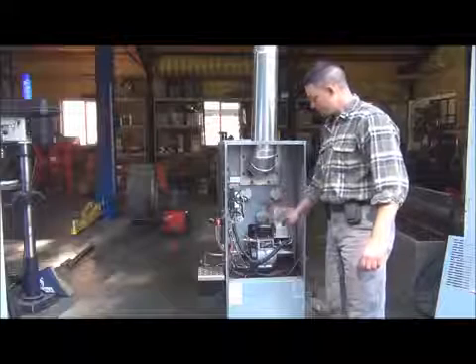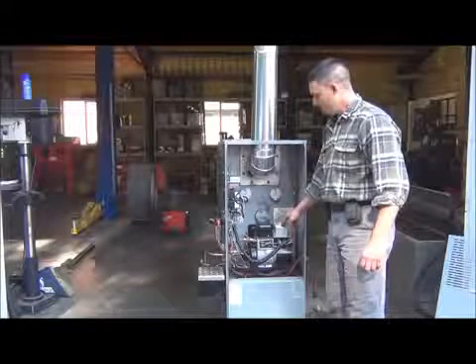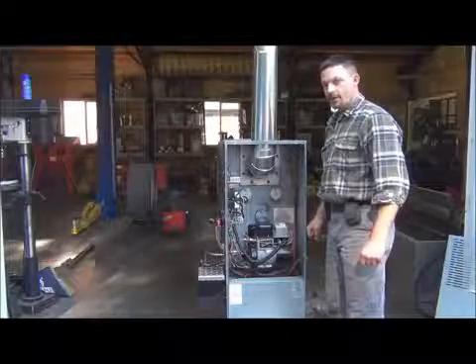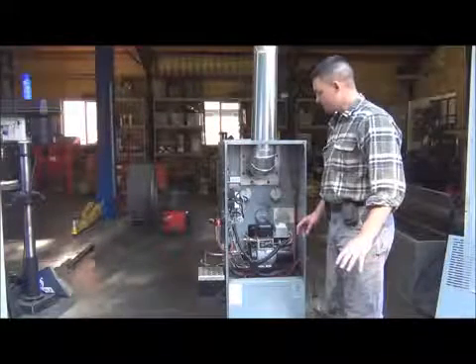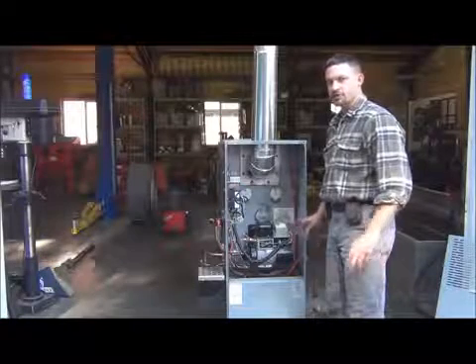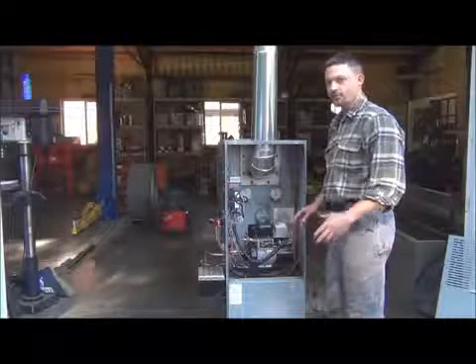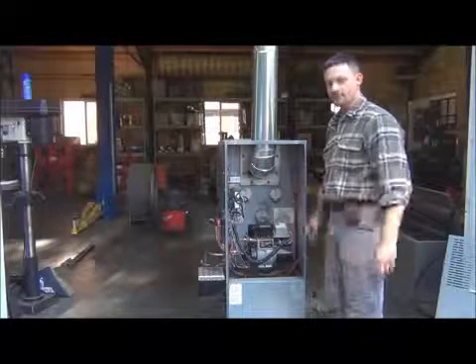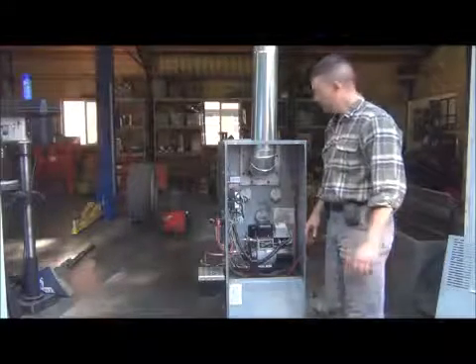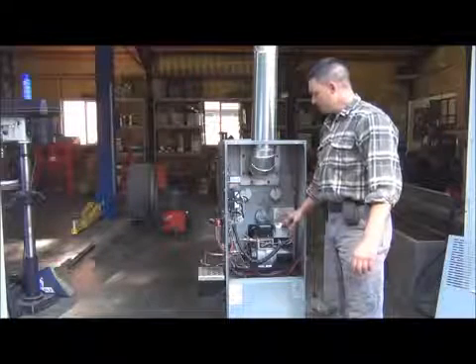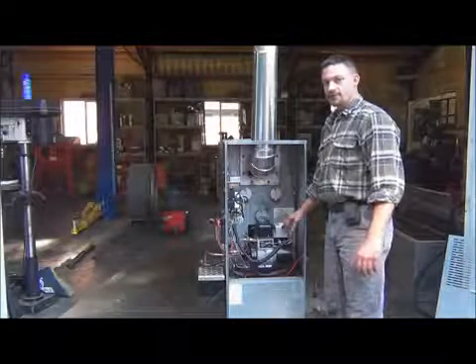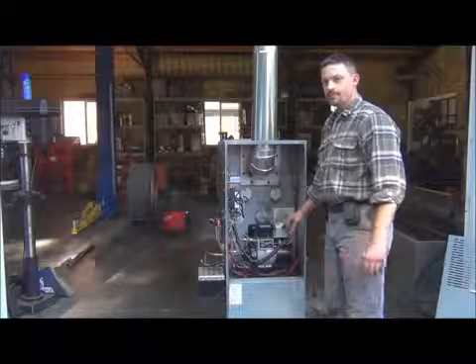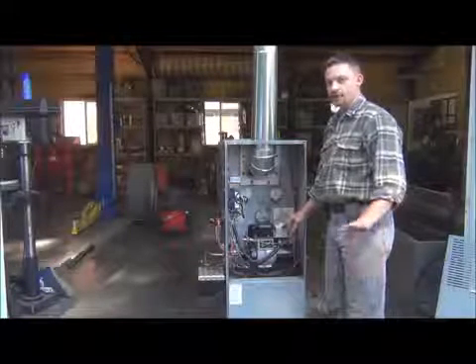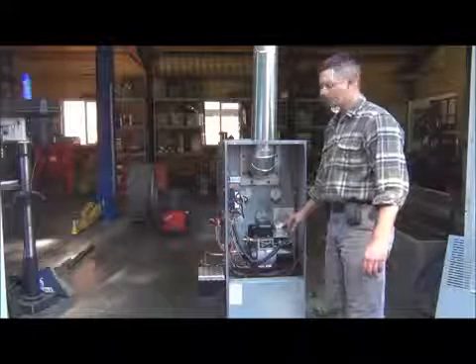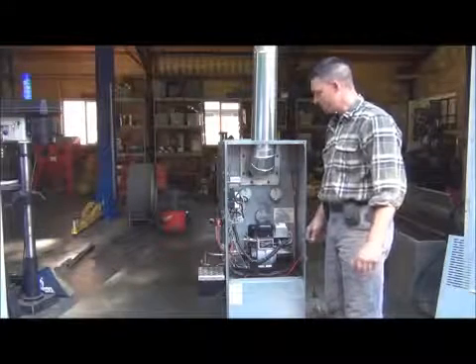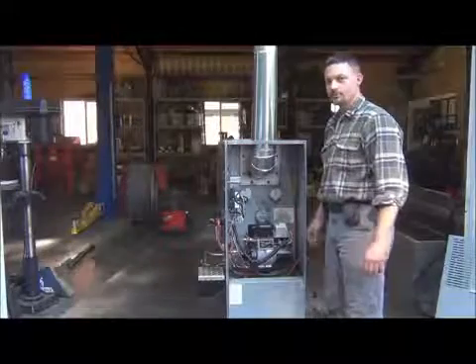And then I've reused the existing primary safety, and what this does is it has a flame detector down inside the tube, and it won't allow the burner to light if it detects that there's already flame in the heat exchanger. Meaning if you spilled some oil in there and there's a fire burning in there that's not supposed to be in there, it won't allow the burner to spray any more fuel in. And what else it does is, if the burner doesn't light when it's supposed to, after a small amount of time, it locks the burner out and prevents it from spraying any more unburnt oil into the heat exchanger. So if you come out here and this red button's popped up, then you know that you got some kind of problem. For some reason the burner wouldn't light.